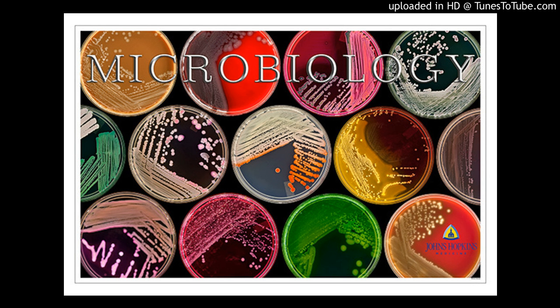This is where you take your instruments that you want to sterilize, you wrap them up, and then you stick them into your autoclave, which is basically a big pressure cooker. It has a chamber that you seal off, and then you pump in hot steam. This steam is usually at about 121 degrees Celsius. This is 21 degrees above boiling, and at 15 psi, pressurized. As we mentioned before, this will break down that outer coating on things like endospores and make it easier for them to be destroyed by this process.